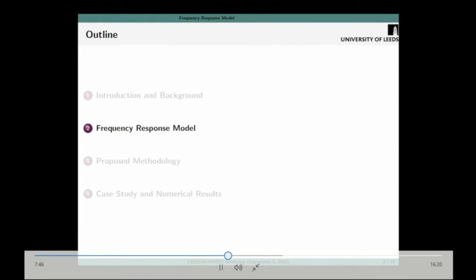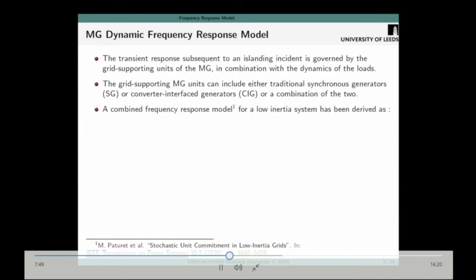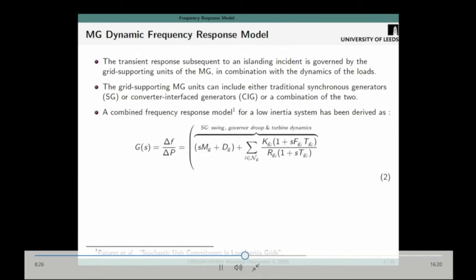In order to do this analysis, we had to adopt a frequency response model. And we know that the frequency response of the microgrid will be governed by the different units connected in the microgrid. For a unit to be able to provide frequency support, it has to have grid support capability, which is physically present in the traditional synchronous generators, but can be emulated in the converter interface units. So from this, we adapted a frequency model in the reference one below because it adequately provided a model that considered both synchronous generators and converter interface units in a network.